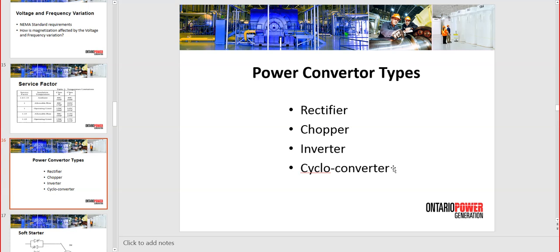Cycloconverter is not so popular. The cycloconverter is for synchronous machines and is changing only frequency. The output frequency can only be less than the input frequency, and it is for large synchronous motors. For large induction motors, you have a VFD that is slightly different than the one described, which is a voltage type. There is a current type that, instead of a capacitor bank in the DC bus, actually has a coil that magnetizes and keeps the energy for the commutation of the IGBTs in the inverter, and that's for medium voltage inverters.